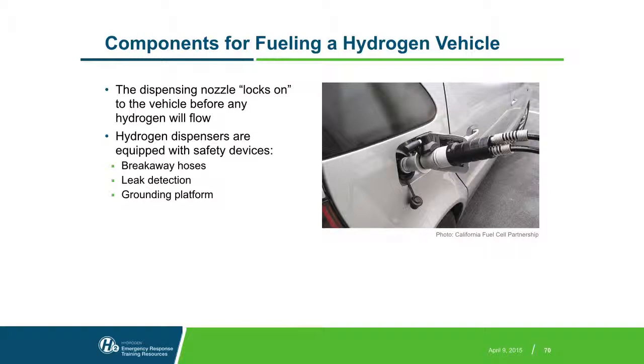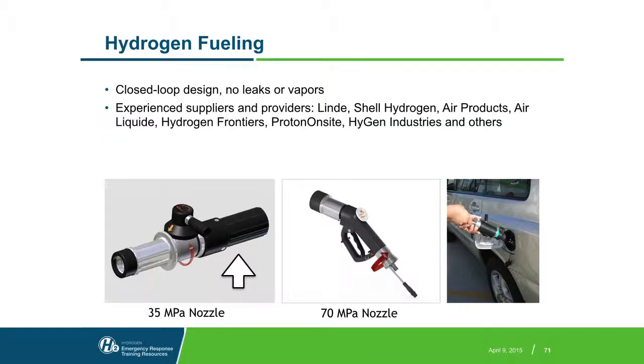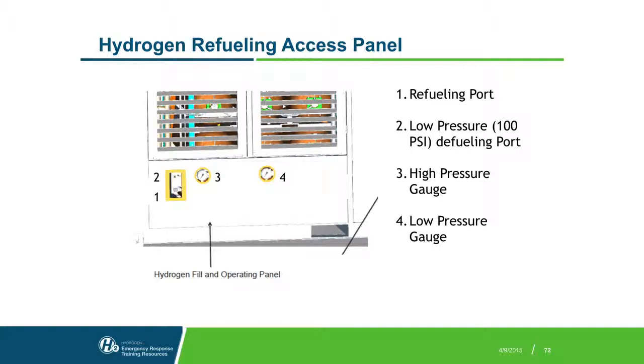And the station, when connected to the unit, should perform a series of leak checks as well, and not fuel if it's not connected properly. It is a closed loop fueling, so any leaks, again, would stop fueling, and this is the nozzle that would be used.